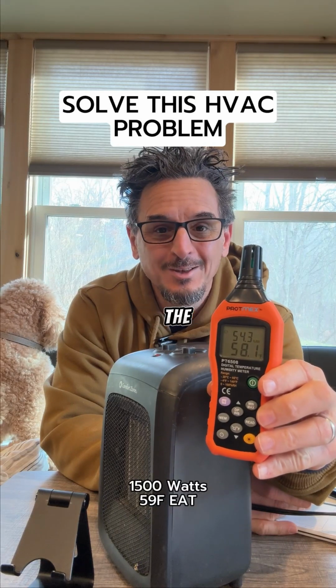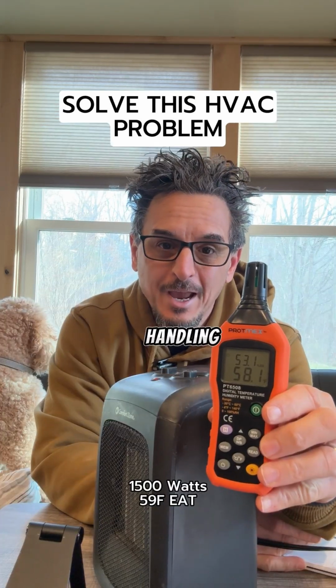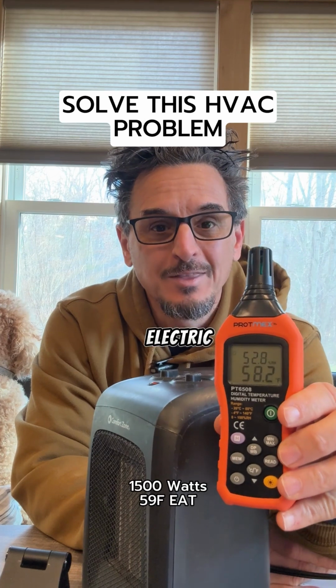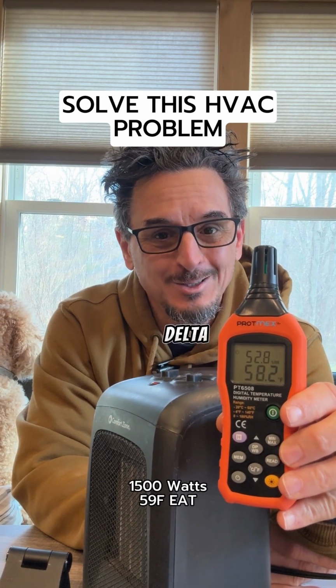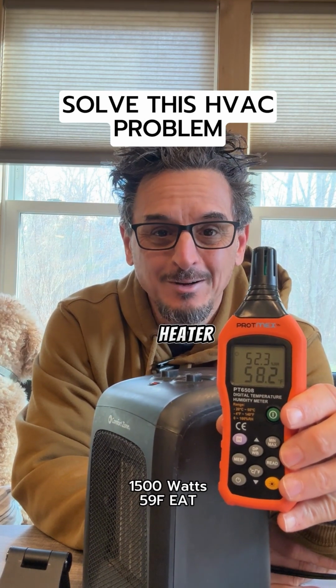Did you know you can calculate the CFM of any air handling unit, provided you know the electric heater's KW and the delta T across that heater? I did not know that.